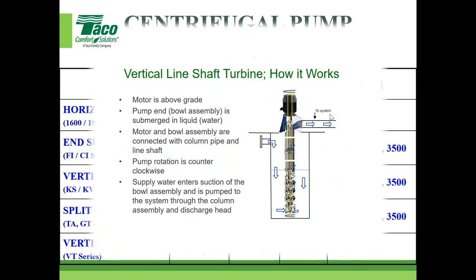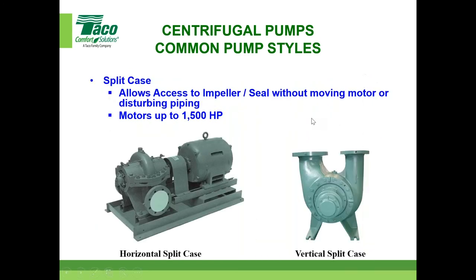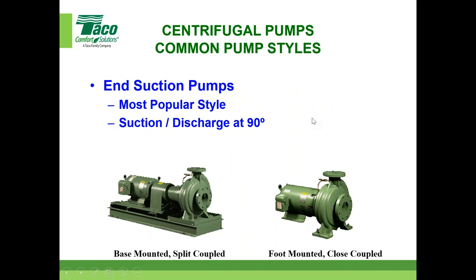Then we have another question. Do you recommend installing a rubber coupling to avoid transmitting vibration from the pump to the piping? And I think they're talking about couplings in the piping system. It's not a simple answer, because the noise and vibration generated by a pump has to be evaluated to see if the pump should be mounted on an inertia pad, because sometimes just putting in a flex connection or a rubber coupling is not sufficient. You have to have an inertia pad sitting on springs in concert with rubber or other types of flex connections on the piping.